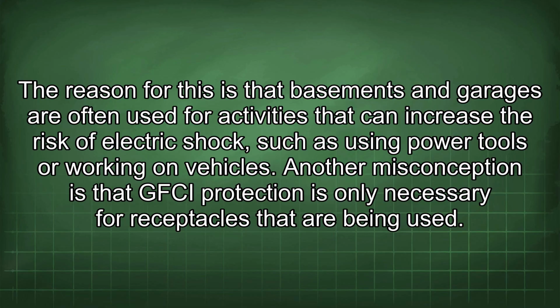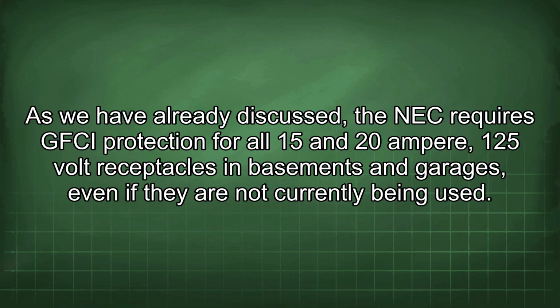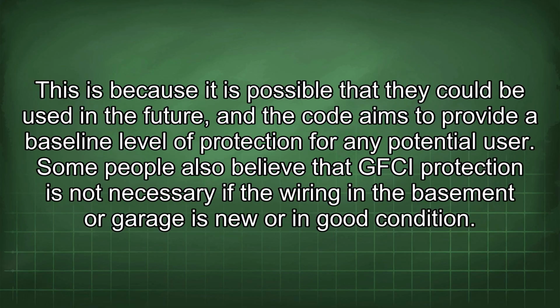Another misconception is that GFCI protection is only necessary for receptacles that are being used. As we have already discussed, the NEC requires GFCI protection for all 15 and 20 ampere, 125 volt receptacles in basements and garages, even if they are not currently being used. This is because it is possible that they could be used in the future, and the code aims to provide a baseline level of protection for any potential user.